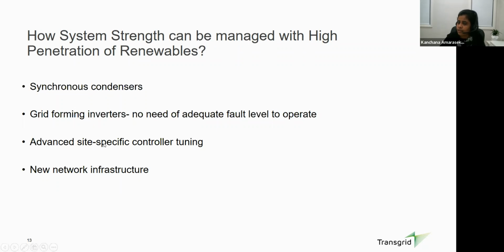The third item I have is advanced site-specific controller tuning. With this tuning, we can manage some controller interactions up to a certain level. It might not resolve all the issues, but it can be used to manage issues up to a certain level. The last item is development of new network infrastructure. As I mentioned, usually we see these issues in the remote parts of the network. So if we develop new network infrastructure, it could reduce the effective electrical impedance, and because of that, it could also help.